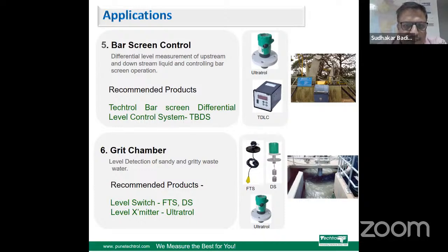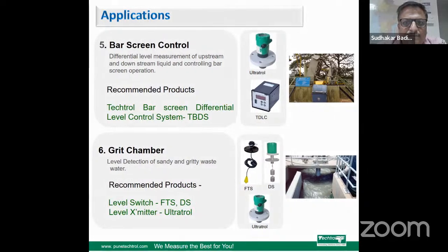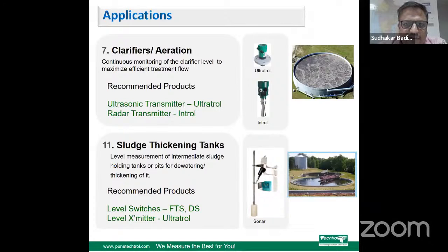These grit chambers are generally used to separate sand and waste from the raw water, which avoids accumulation in the pipelines and channels, and also protects the pumps from different types of solid particles. So here in the monitoring, we use these switches and transmitters. Then for clarifiers and aeration, we have non-contact radar level transmitters and economical ultrasonic level transmitters like Ultratrol. Then sonar systems for sludge thickening tanks, mostly used for underwater sludge blanket detection.